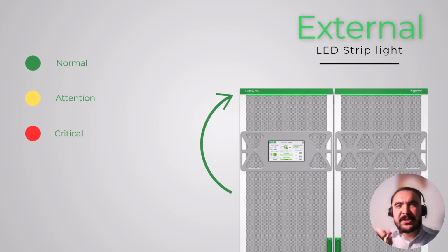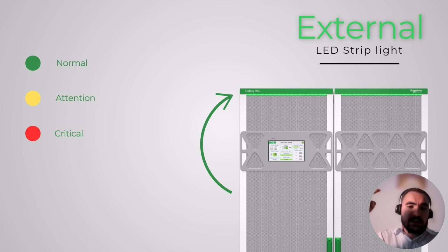One of the most useful added features of this Galaxy VXL UPS is that it contains an exterior LED strip light attached at the top of the UPS, showing you the UPS alarm status without the need to go to the display and navigate through settings. Now you can walk far away in the facility and take a look at the UPS: if it's in good condition, it will pulse green light; if it needs attention, it will pulse yellow light; if it's in critical condition, it will pulse red light.